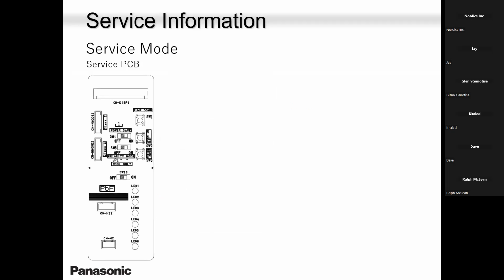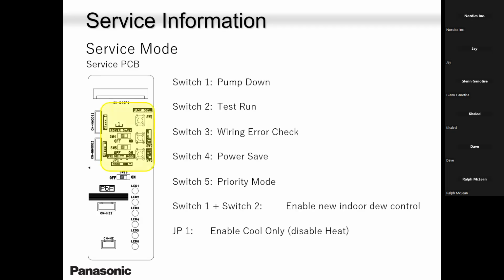So this card, you will not see it in our single zones, okay? It's just designed for multi-zones. So don't expect you to open the outdoor unit and say, oh, there's something missing. No, it's only for multi-zones. So SW1, guys, at the very top is pump down. If you want to pump down the system, collect all the gas into the outdoor unit, it's SW1. SW2 is test run. SW3 is wiring. 4 is power save, and 5 is priority mode.